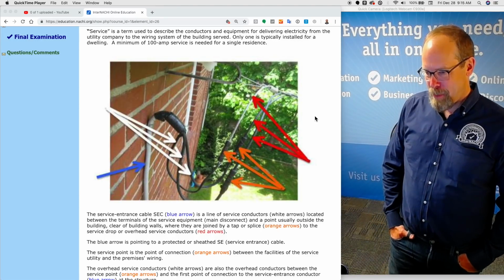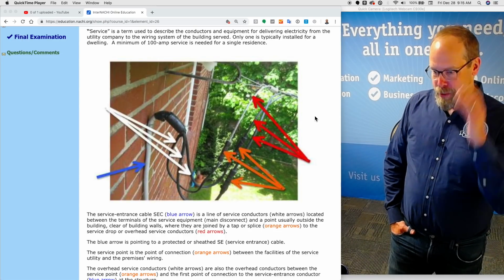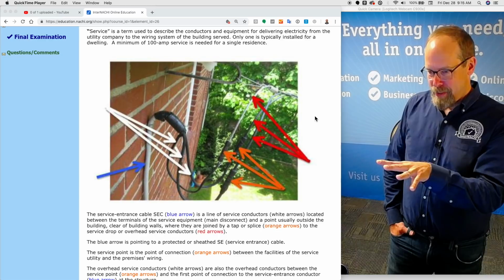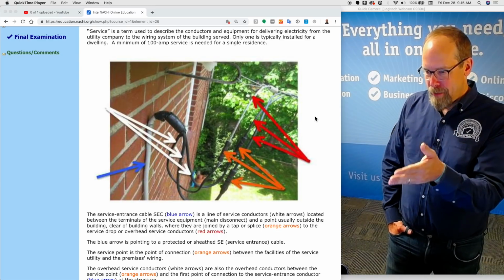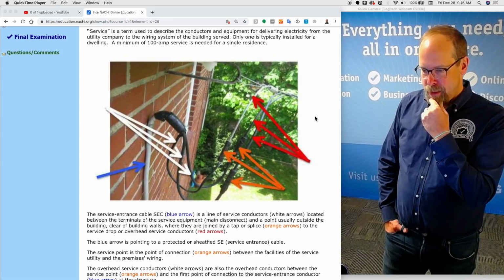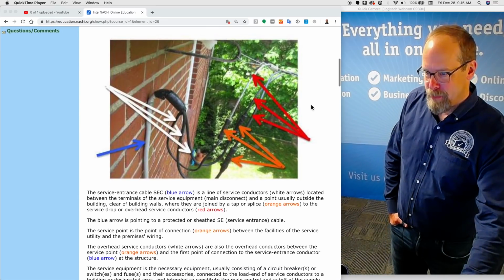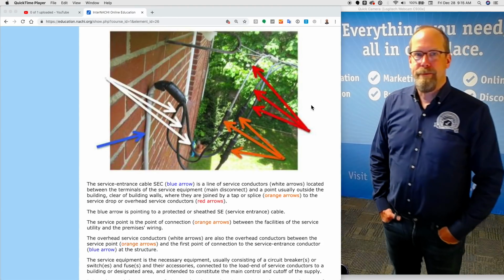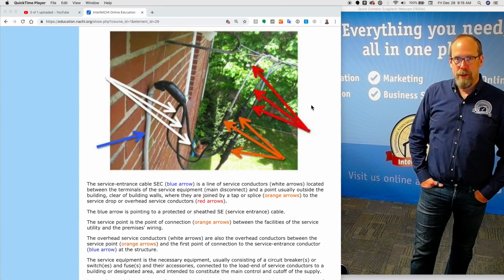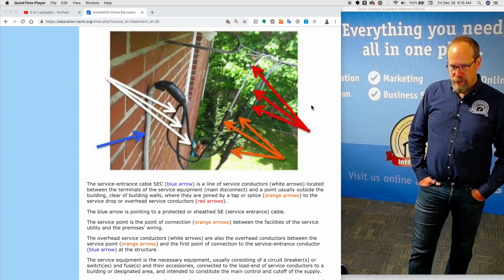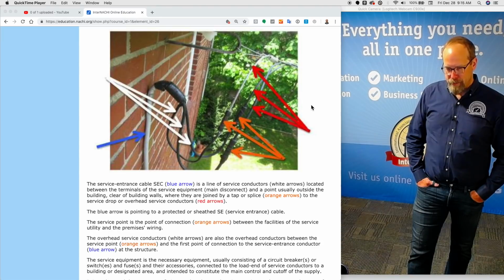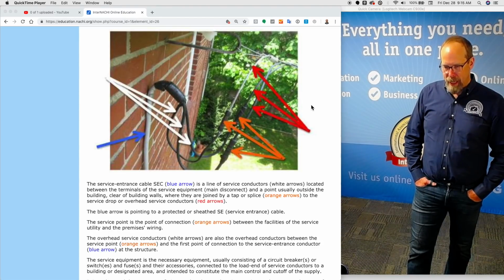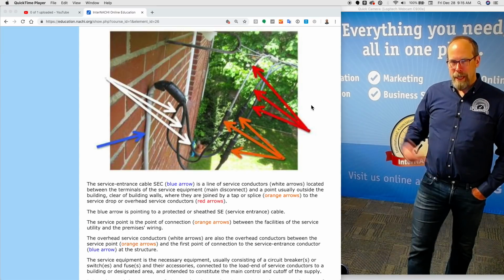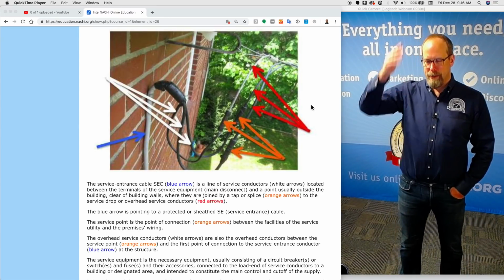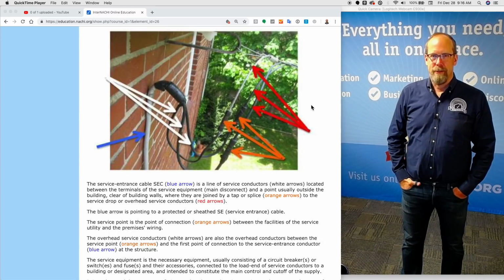Now take a look at this inspection image. There's a few parts, components of this area. There's a blue arrow, white arrows, orange arrows, and red arrows. Let's go over them and identify them so that you're using proper terminology during your inspection and within your inspection report. The service entrance cable, SEC, that's the blue arrow right there. So it's pointing to the SEC, the service entrance cable. And that's that line that's, for me, usually attached to the side of the house, on the outside of the house, and it goes right into the top of the meter box, right?